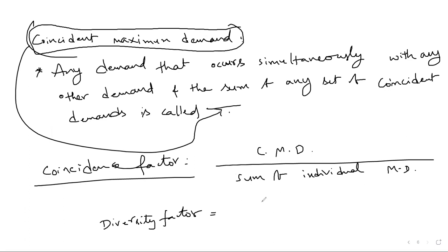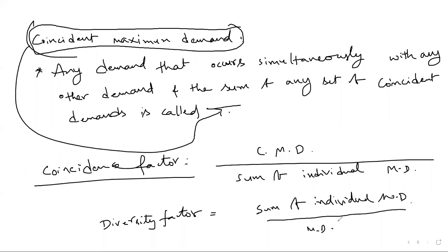Maximum demand by total connected load. No, that is the demand factor, Sirisha. Maximum demand by total connected load, that is demand factor. What I am asking is diversity factor. Nothing but sum of individual maximum demands by maximum demand of the complete system or power station, right?